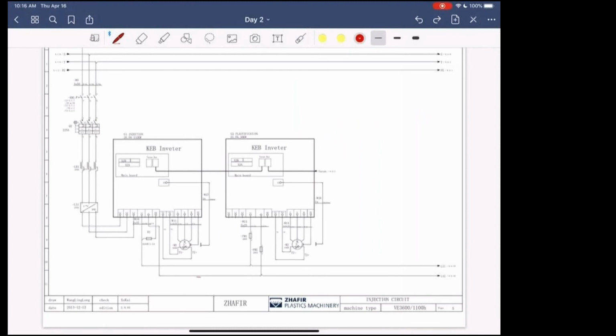So it takes the signal from three phase, line 1, line 2, line 3, which is an AC 60 hertz signal, and goes into this rectifier system. That converts it to a DC signal. So eventually, after it's done going through the whole converter, it'll actually be a solid DC signal.